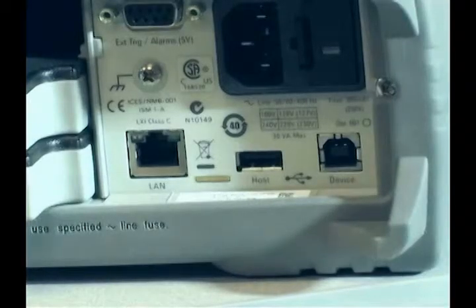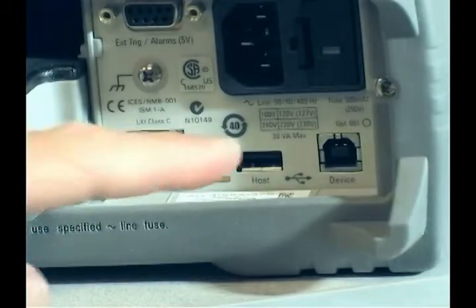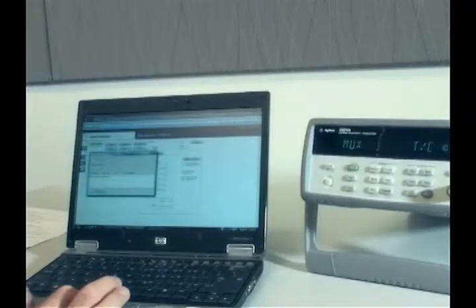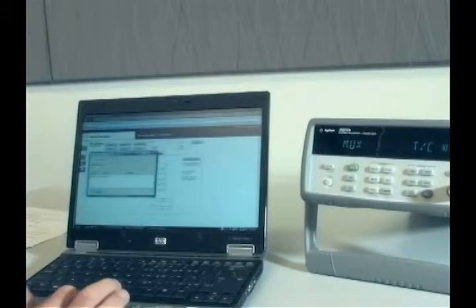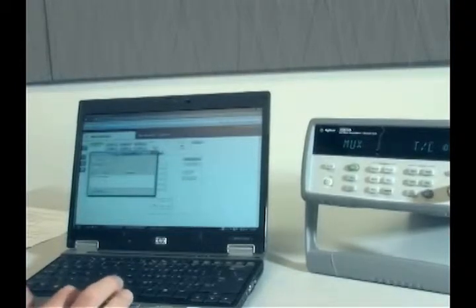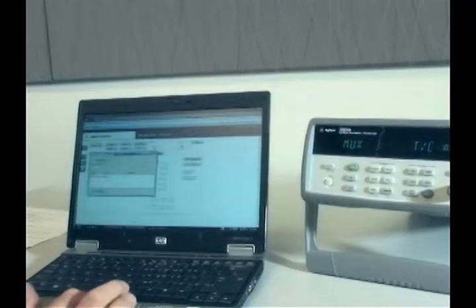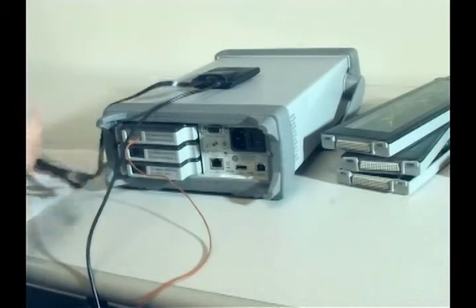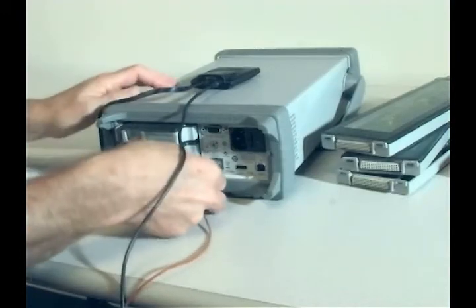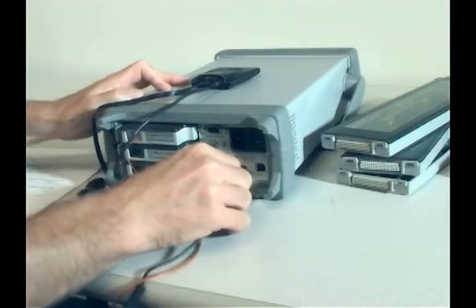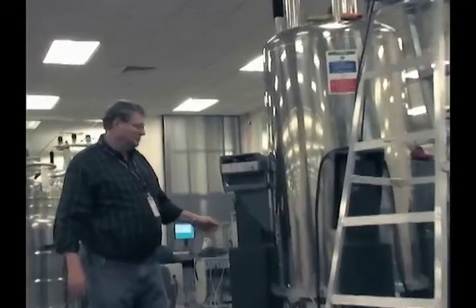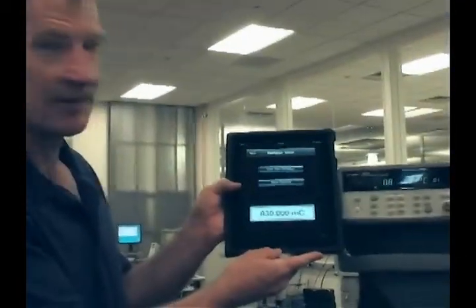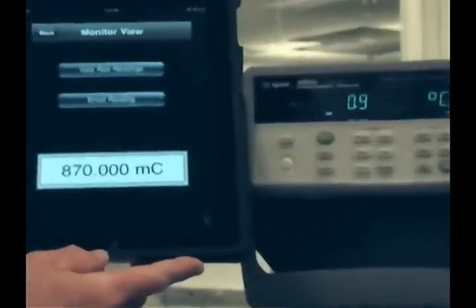The difference between the 34970A and the 34972A is that the 34972A features USB and LAN. The LAN port allows you to access a web server built into the 34972A using just a PC and a browser. Adding the travel router enables wireless LAN connectivity, and it can be powered by the 34972A's USB port. It's nice to be able to connect wirelessly, as we are often separated from our data acquisition unit due to noise or equipment placement — either behind glass or halfway around the world.